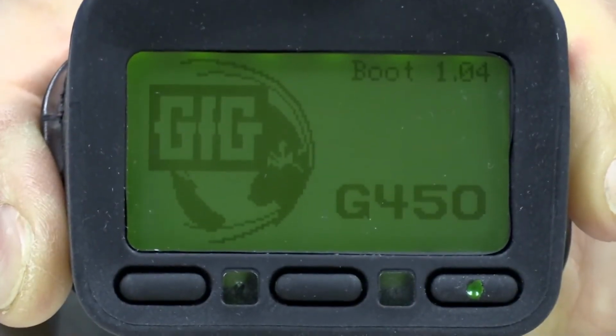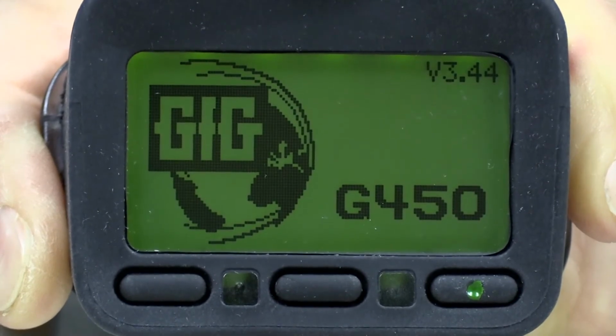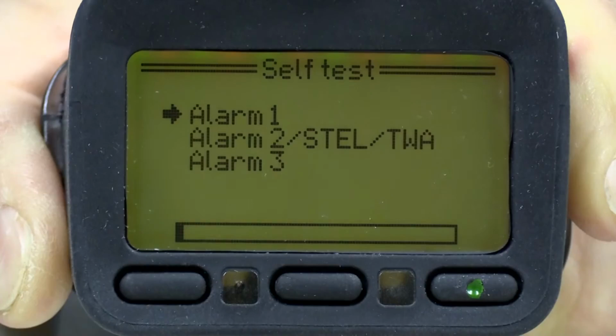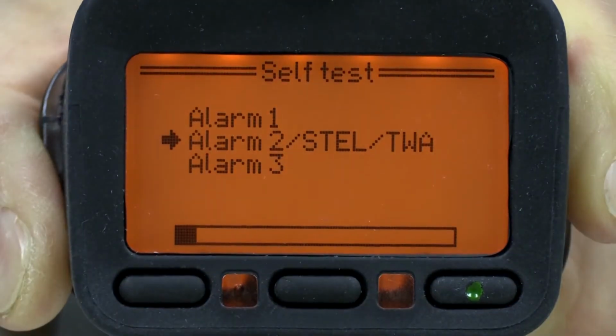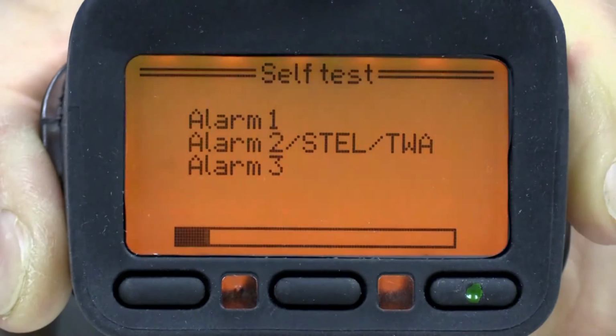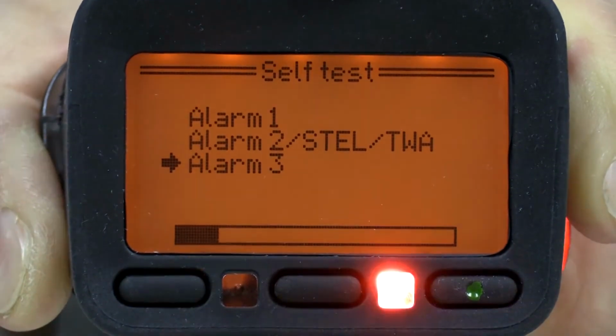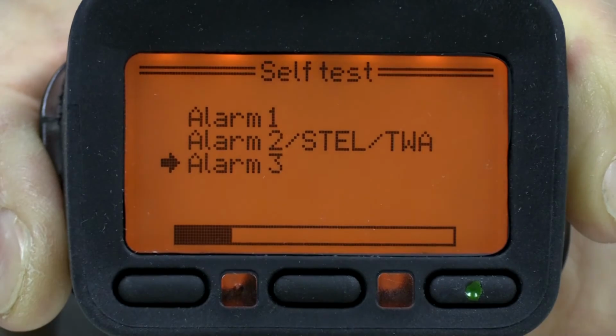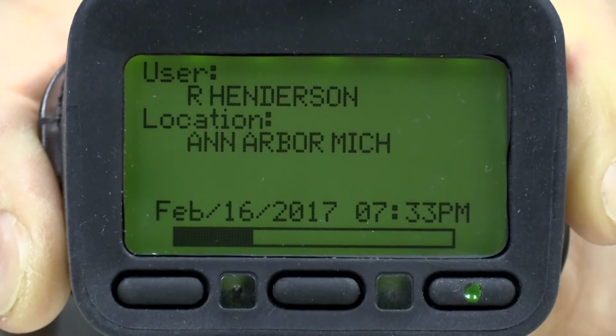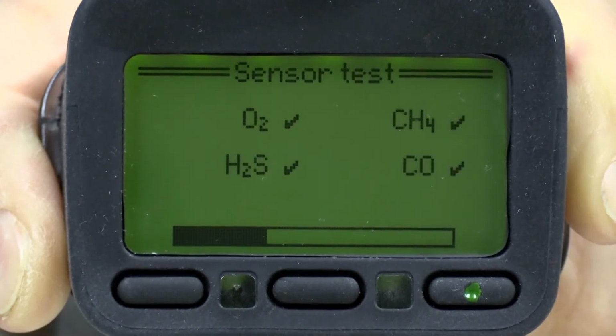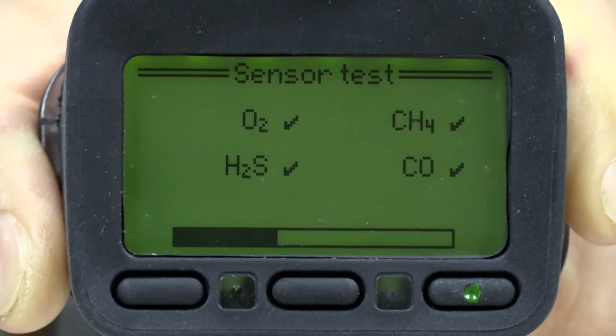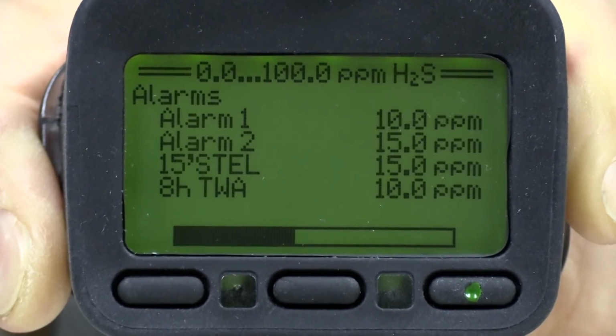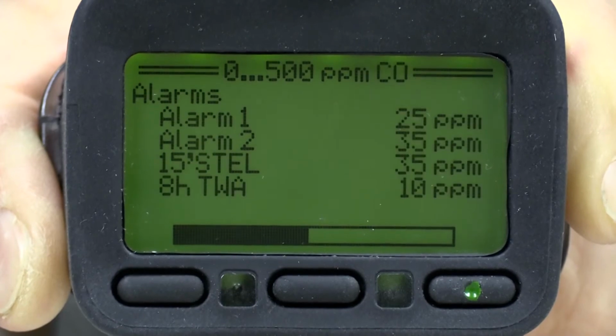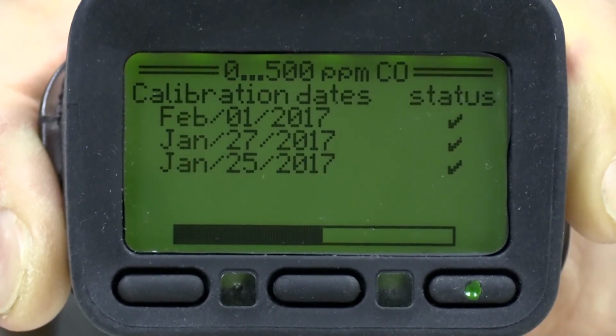After turning the instrument on, it will display a sequence of information screens while it's warming up. The first screen in the startup sequence shows the software version currently installed. The audible and visual alarms and the vibrator alarm will briefly activate, and additional screens will show the operational status of the sensors. If the instrument has been programmed with the information, it will also show user ID and location ID. The startup sequence will continue with screens showing the alarm settings and the most recent 3 calibration dates for each sensor.